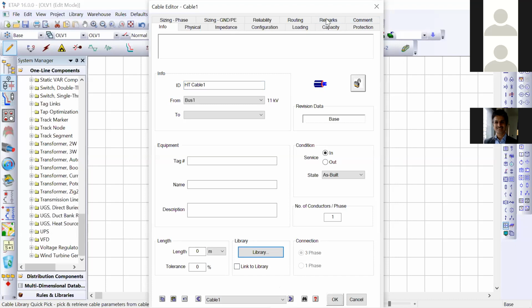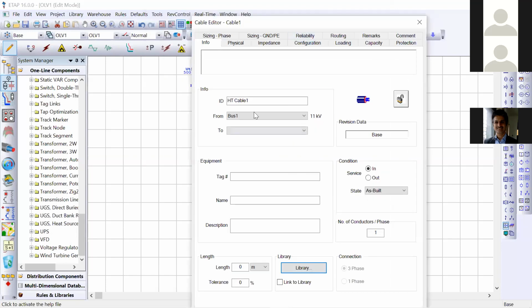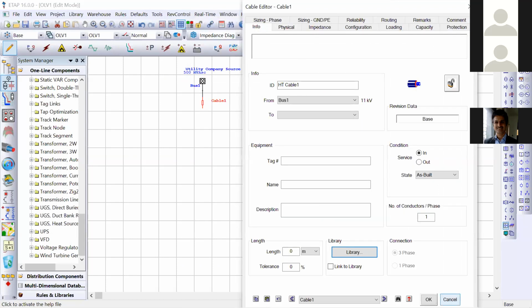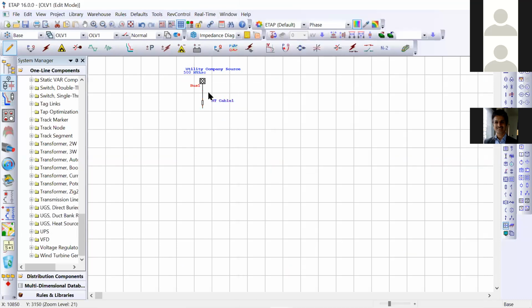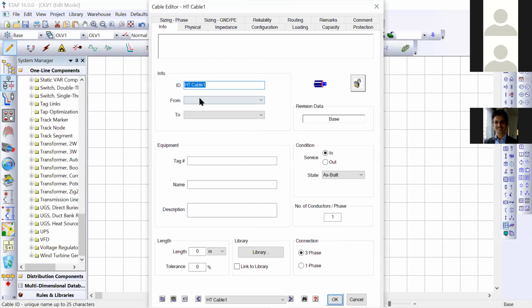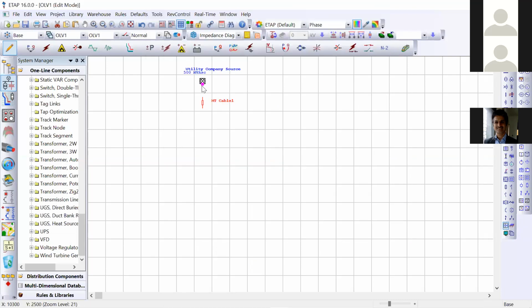Now, see, this is the facility of ETAP software. This is the HT cable I have entered from bus 1. This bus 1 is taken automatically because I have created this link. If I remove the link by deleting it, this is gone, because the software doesn't know where to connect this element. So it is better to first have a connection between these two elements and then double click it.